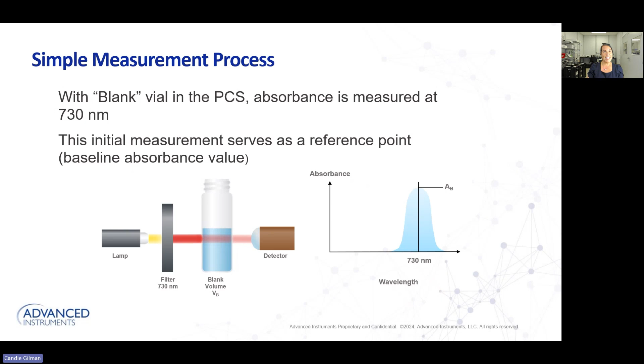we start with a blank vial. So the blank vial has blue dye in it. And what happens is when I insert that blank vial into the instrument, there's a 730 nanometer filter that reads the absorbance of that blue dye and provides, based on the wavelength, a baseline absorbance value for what's getting ready to happen. And then I come by with my pipette.